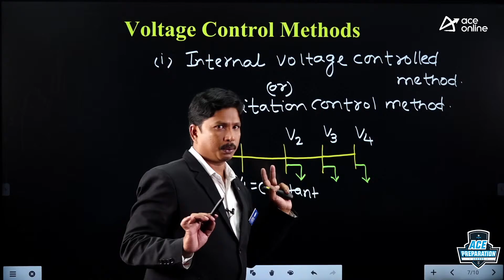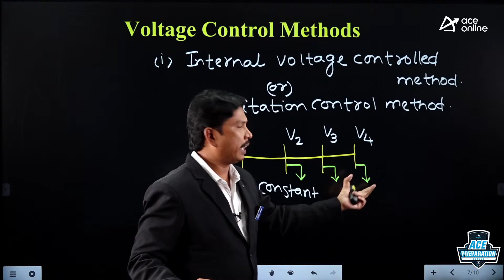Therefore, whenever we have some problem at V4, we are going to control the sending end voltage, that is the excitation voltage. This generator has an excitation, so we are going to control the excitation of the generator. Suppose V4 is less, we will increase the excitation voltage, then automatically the V4 value will be increased. Whenever V4 is more, we will reduce the excitation voltage, therefore V4 will automatically be reduced.